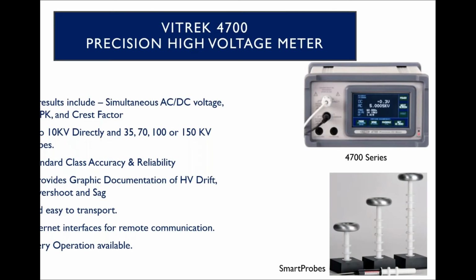And so now I'd kind of like to lead into the Vitrek 4700 high voltage meter. So this device is used in standards and calibration labs around the world right now. Basically, it includes measurements as AC and DC voltages simultaneously right there on the screen, along with your frequency, your peak to peak, and your crest factor, all the time right there on your digital display. So it measures up to 10 kV directly and 35, 70, 100, or 150 kV with the additional smart probes, which are developed specifically for use with this 4700. It provides laboratory standard class accuracy and reliability.